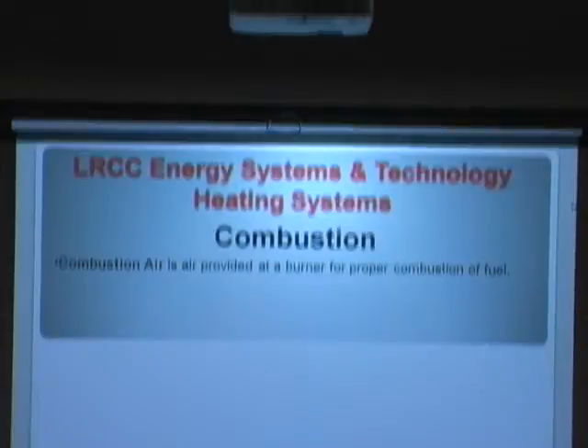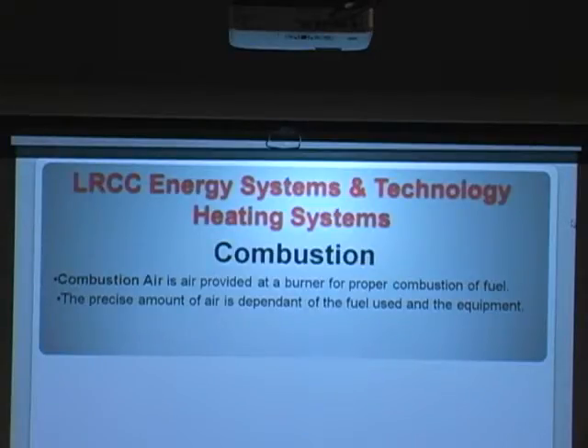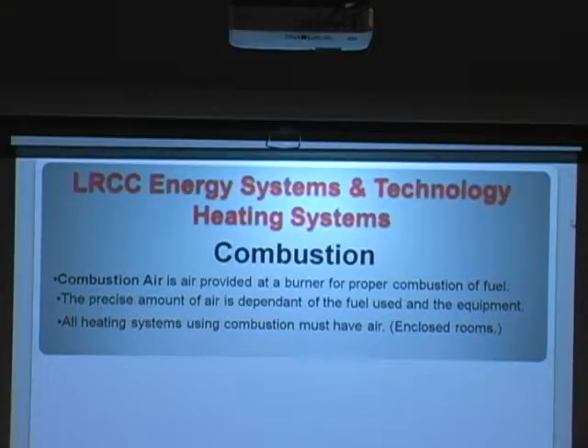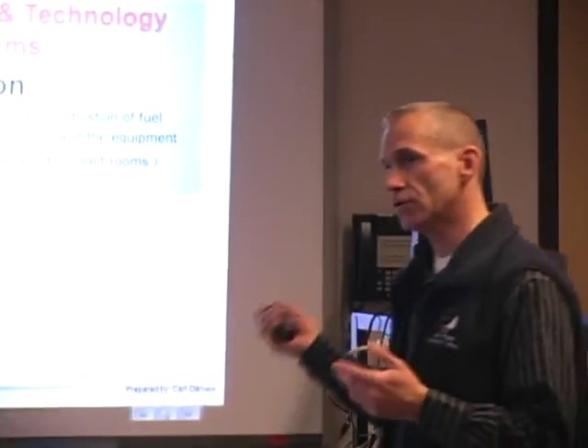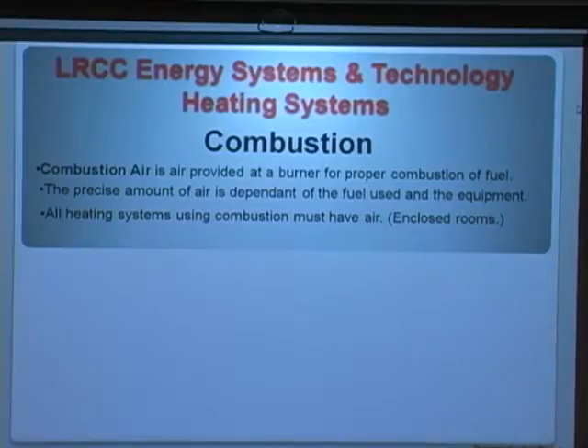Combustion air is what we're primarily going to talk about in terms of the oxygen being introduced to the triangle. Combustion air brings that oxygen to the fuel. The precise amount of air depends on the fuel being used in the equipment, and all heating systems using combustion must have air. If you put a combustion appliance — a water heater or heating appliance — into a room and completely seal it so it's airtight, that appliance will not have the necessary oxygen to maintain combustion. You'll see in a little bit why that can become a huge issue.